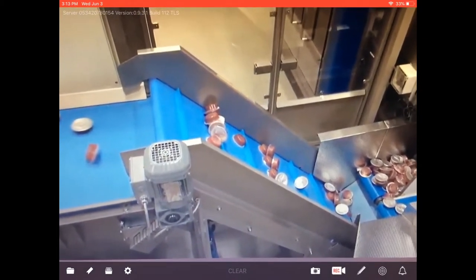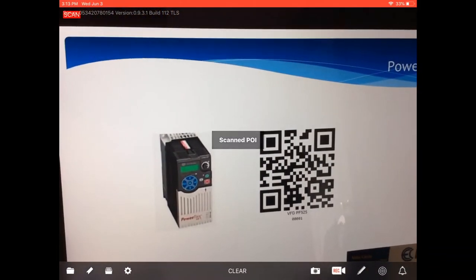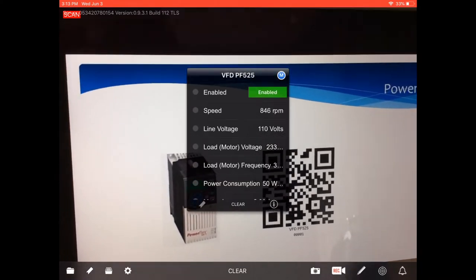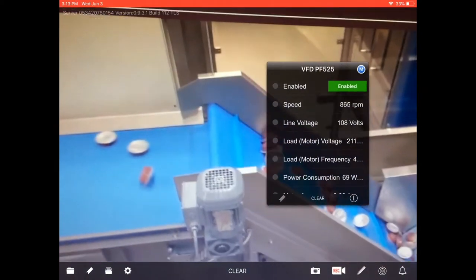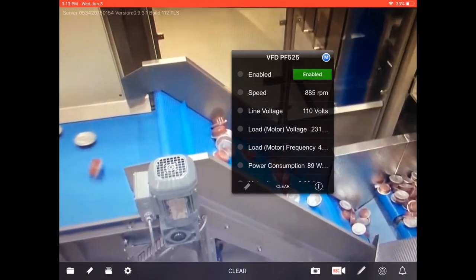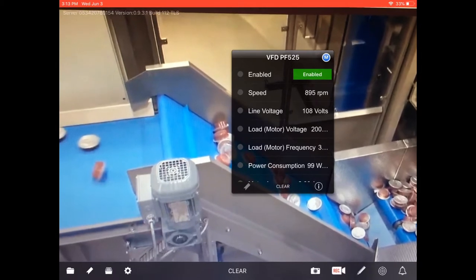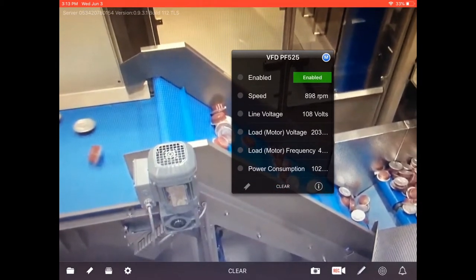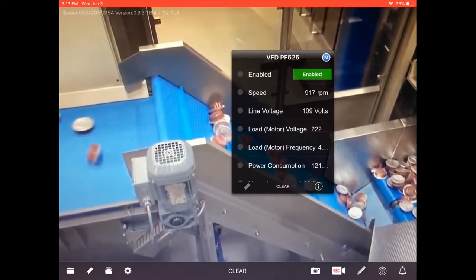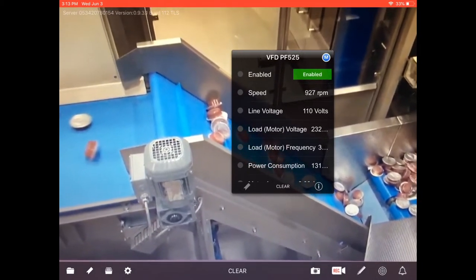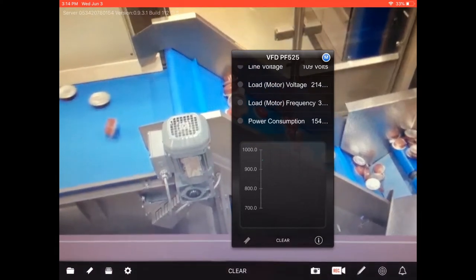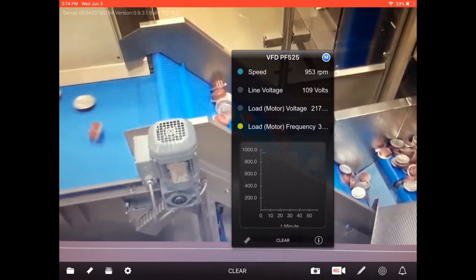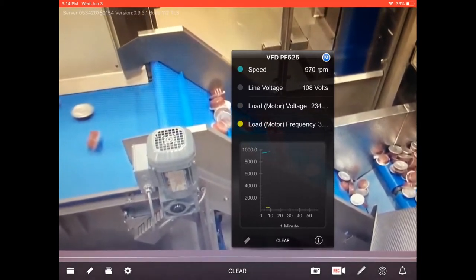First we want to get information on the motor on the left-hand side. I move my iPad over to the QR code on my other computer screen, and that pulls up a faceplate that IQ Agent populates with live data. Right over top of this motor, I can see the conveyor moving, motor spinning. I can see parameterization coming out of the drive. I can scroll through the different values — full load, motor amps, RPM, voltage, etc. — whatever I choose to configure in this faceplate. I can also click on speed or load frequency and trend those values in real time right on the faceplate.